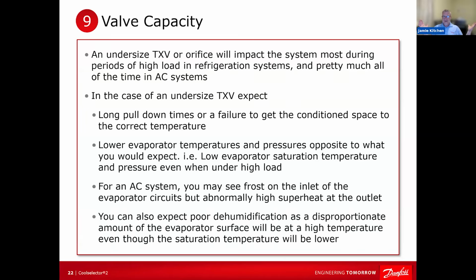And it's correct, right? However, if I ask them what happens next, they probably can't answer that because they do not see it from a system-wide standpoint. Whatever that TXV does, it isn't in a vacuum, right? If it puts more refrigerant into the evaporator, the compressor then has to pump more refrigerant. That's adding more energy to the system. And so your entire balance then gets thrown off.